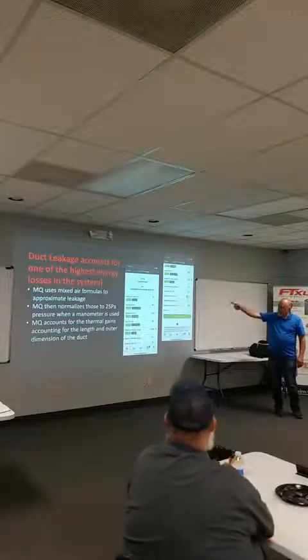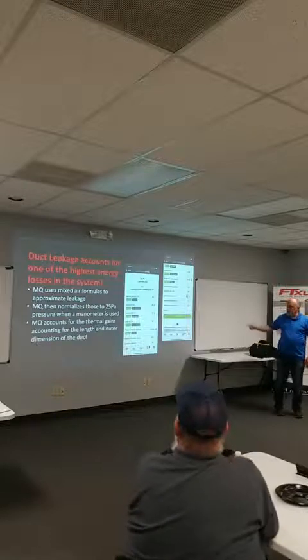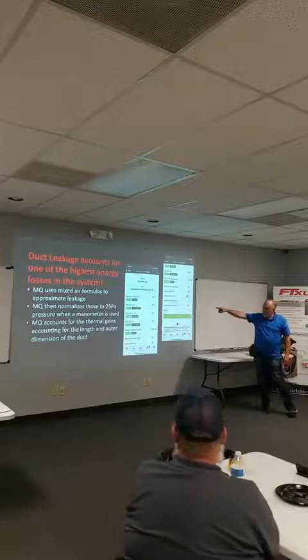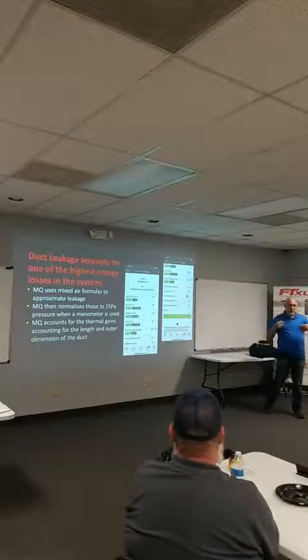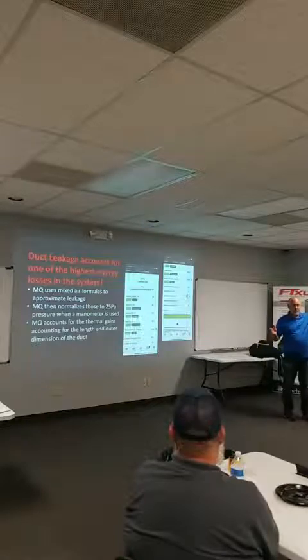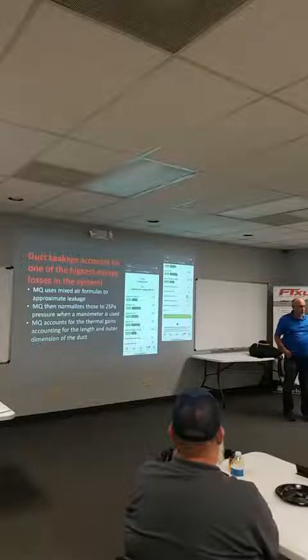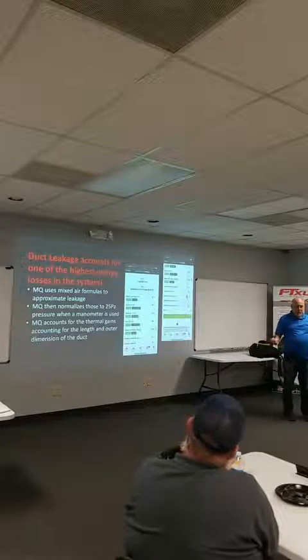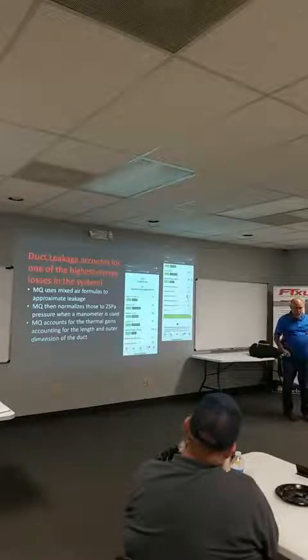Now, going back to this, this is just the mixed air formula. So you have a return air dry bulb, you have mixed air on each side. Now, this is where I'm going back to: I put duct systems on, and I said, well, I'm going to pipe hot air from one of my furnaces right into the return, just to simulate attic leakage, right? So the kids go over there, they're running the furnace, and they put the probe in the return air grill, and it's reading 72 degrees, right?